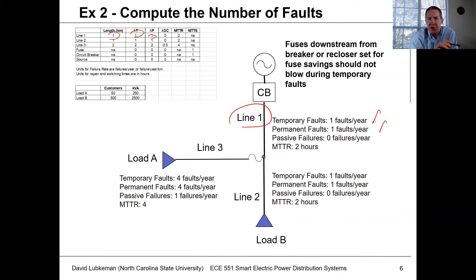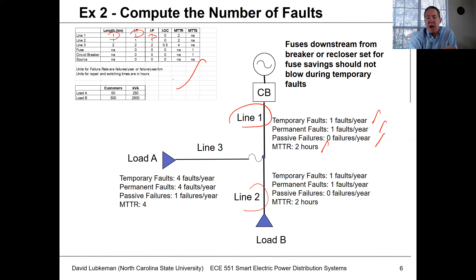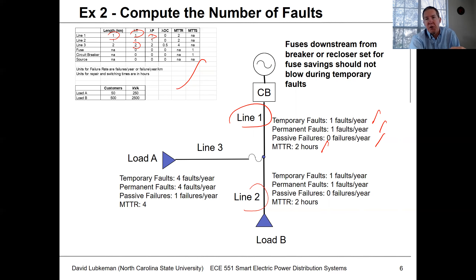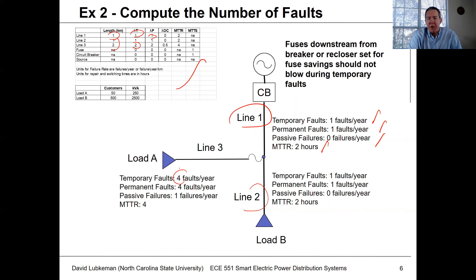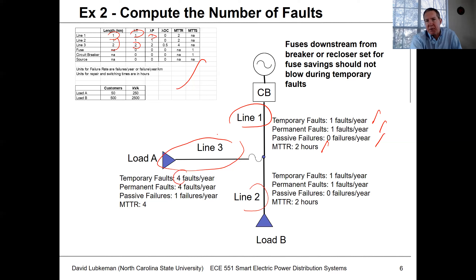These don't have to be rounded integer numbers — they can be floating point. We have no passive failures for some segments. For line section three, we have two temporary faults per kilometer per year; multiplied by the two-kilometer line length, that gives four faults per year. Similarly, four permanent faults per year and one passive failure per year.